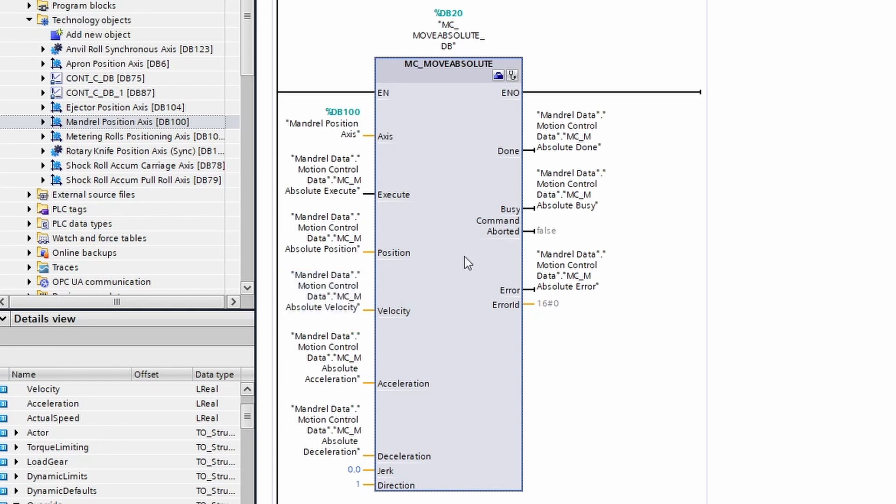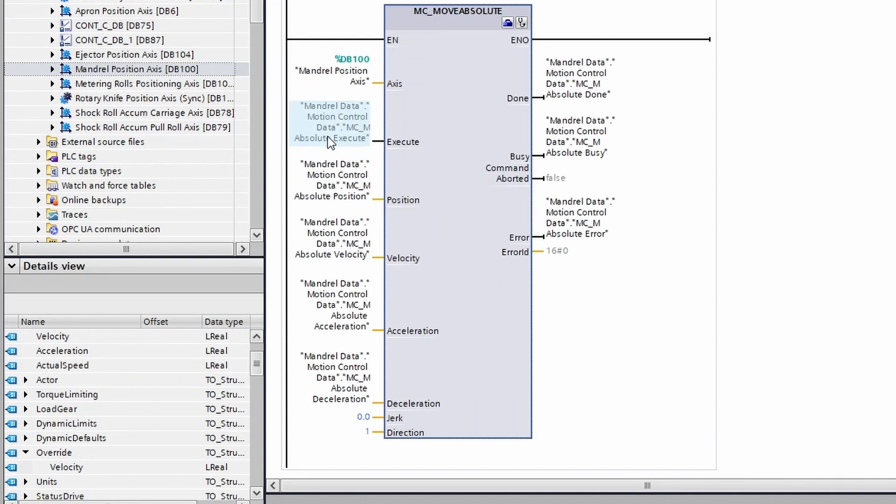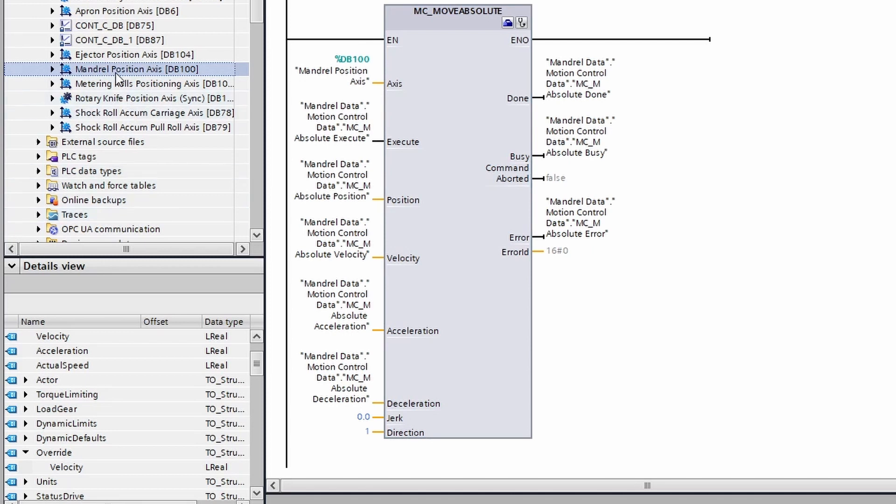As we mentioned in the previous episode, if you're wanting to change the velocity of the move, instead of changing the velocity and executing a new move, you can just modify the override velocity available in the positioning axis under override and velocity.